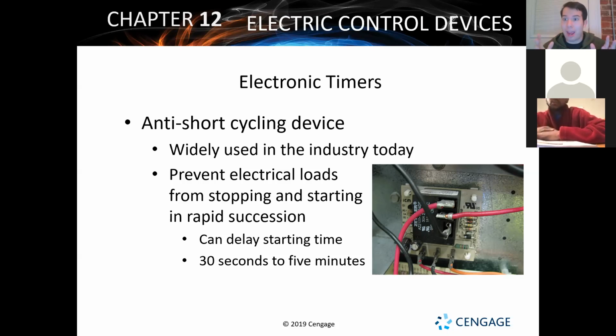But to prevent that from happening just because a system has an issue with airflow or a fan motor not working or something like that, the short cycling device is really just there to make sure there's a set amount of time that this compressor and this system have to wait prior to trying to fire up again. So it's very much just like the other electronic timers we've seen before. It's just specifically purposed for short cycling. It's not so much a time delay sometimes, as some of it will be sensitive to current, but typically it's going to be time, as with most of them. They can be set anywhere from, say, 30 seconds to 5 minutes. 5 minutes is going to be your standard.